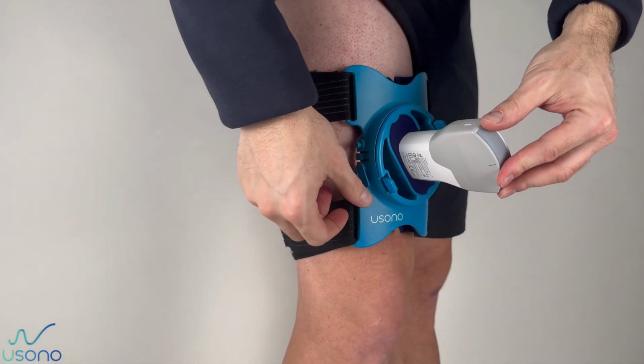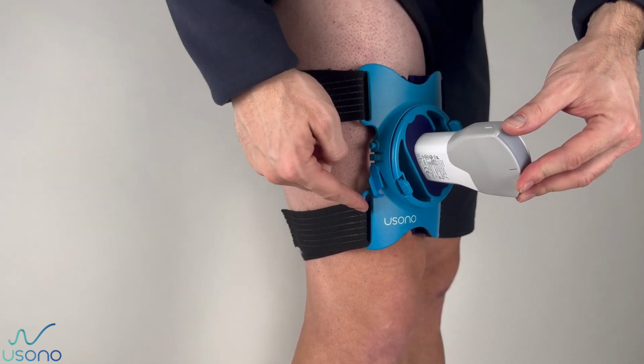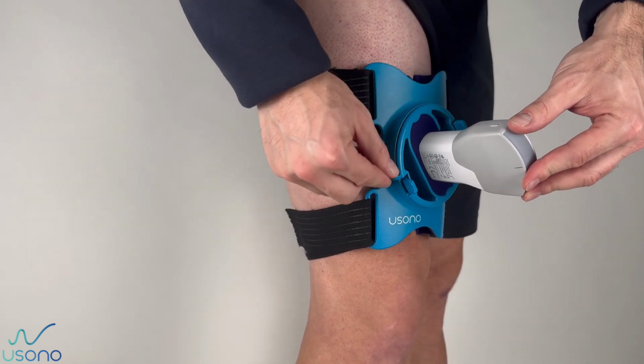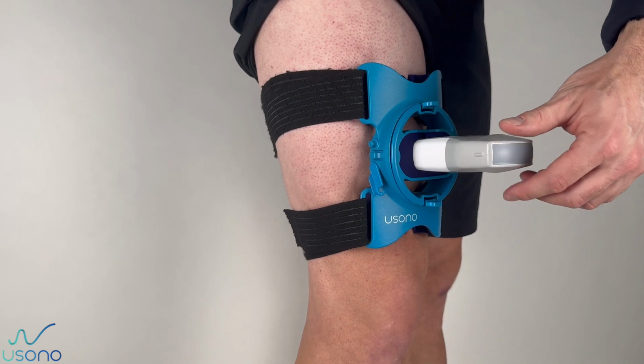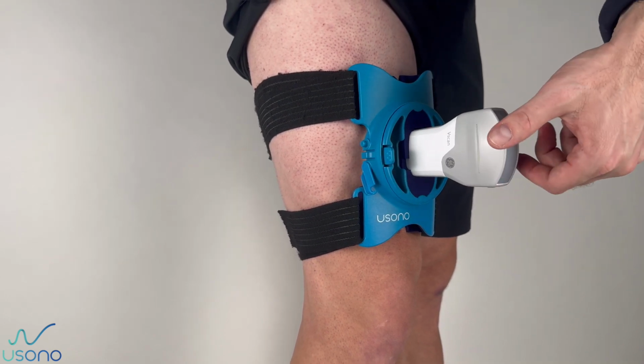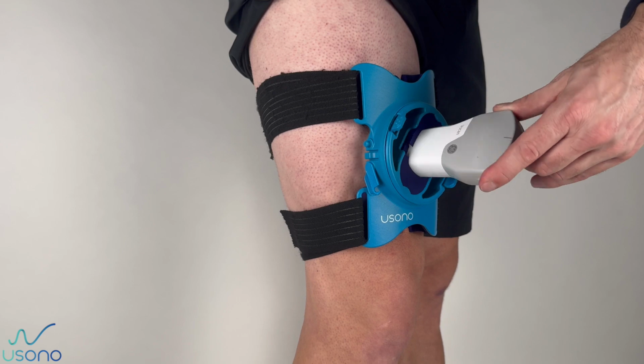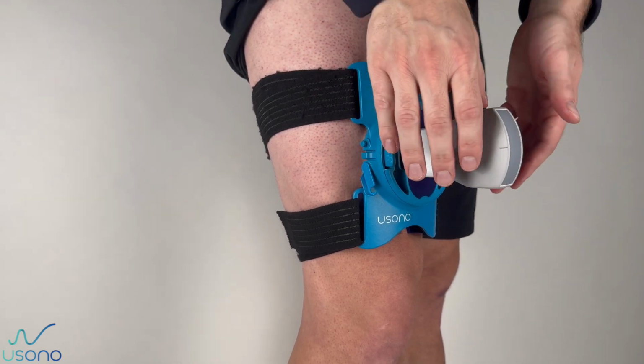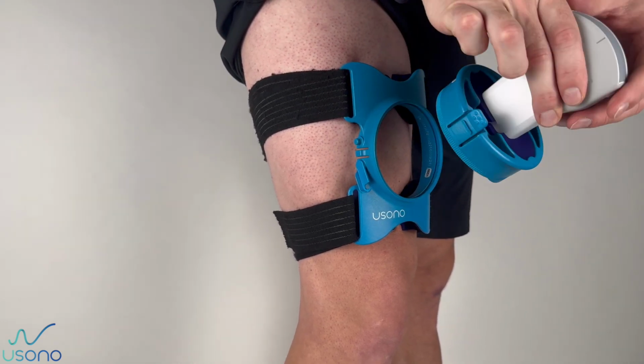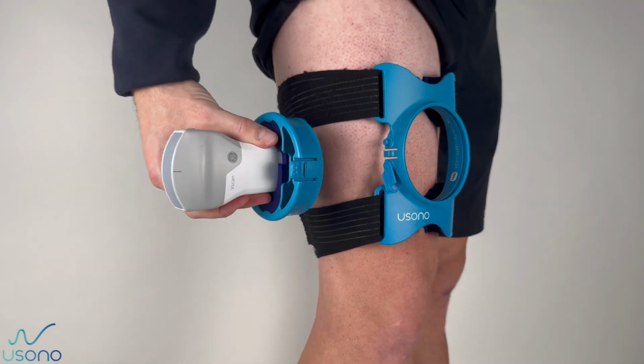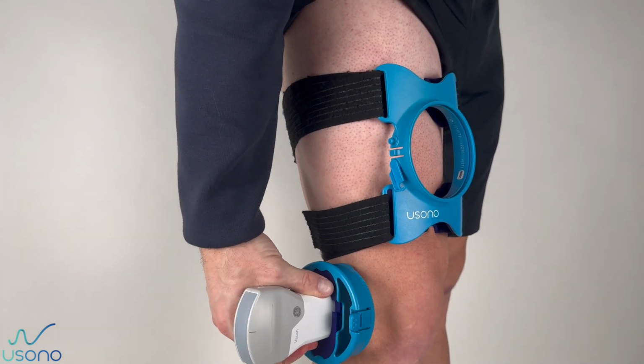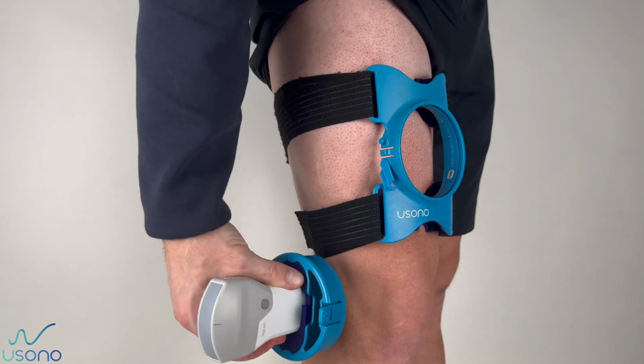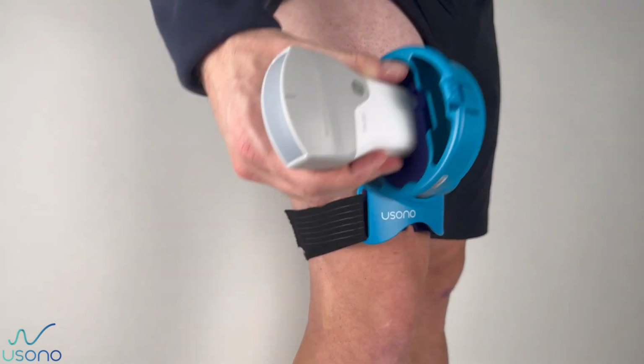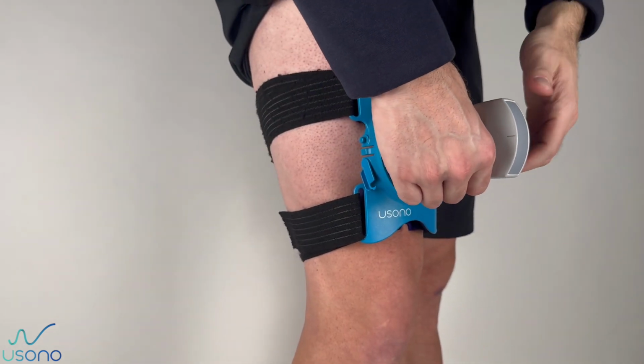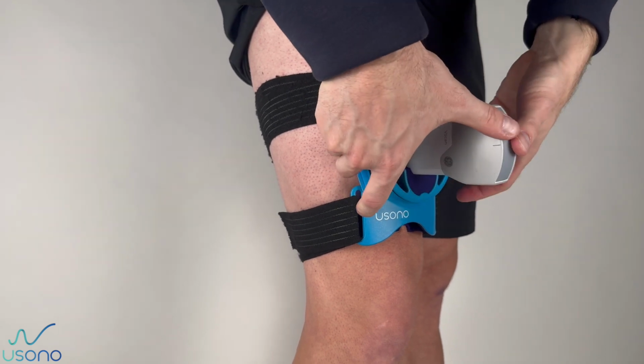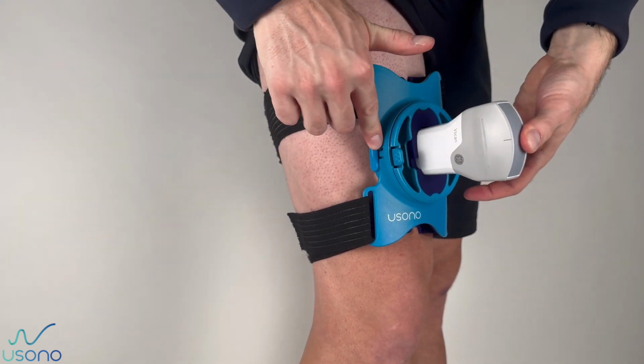You can secure the probe by closing the lock on the side. When the lock isn't secured, you can easily rotate the probe in a transverse and longitudinal plane or any other angle you need. You can even take the probe out to scan a different location. If you're satisfied with the view, fix the angle by pushing the lock down again and the probe will be secured and won't move anymore.